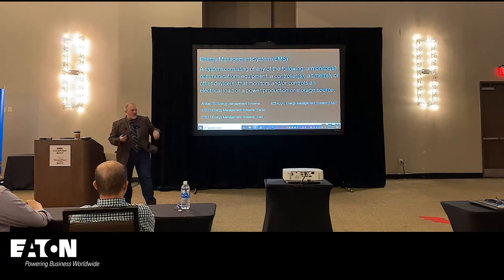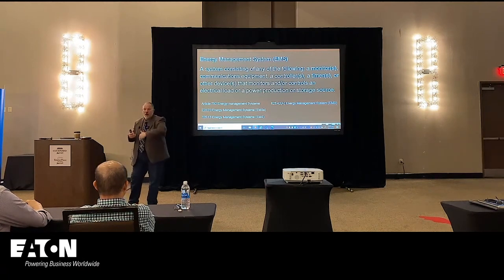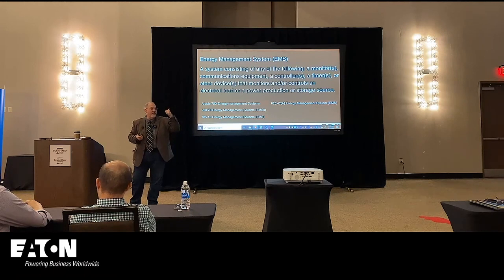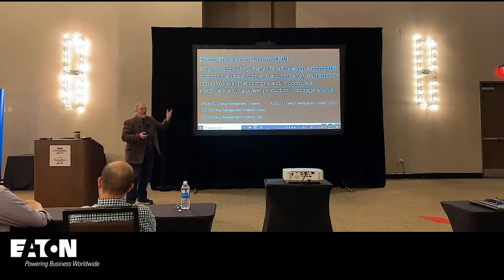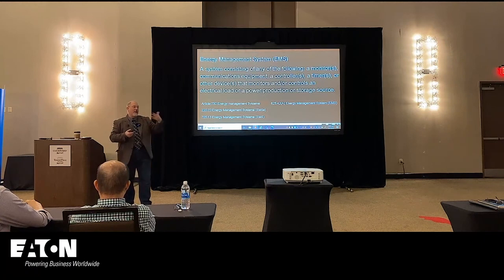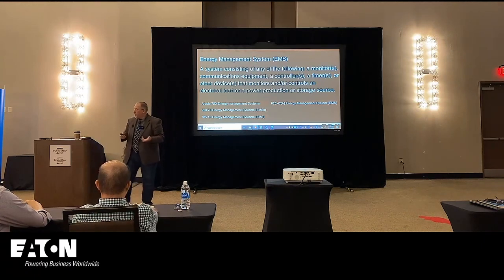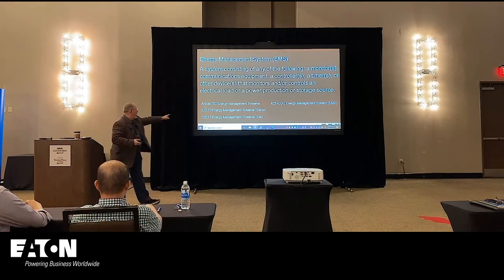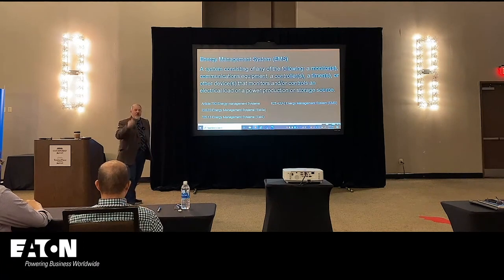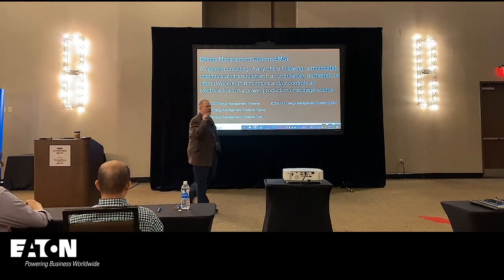So I have a phone. On my phone, I can look at how much energy my outside lights and my inside lights are using at the house, and I can turn them on and off. It drives my wife crazy when I'm remote and I demonstrate it to somebody. But technically, I meet the definition because I monitor. I mean, all I have to do is monitor, and they call it an energy management system. But the way they use the term elsewhere in the code, in Articles 750, 220, 705, 625, a very important aspect of an energy management system is that it has to control the loads.